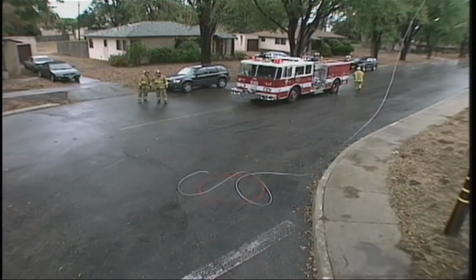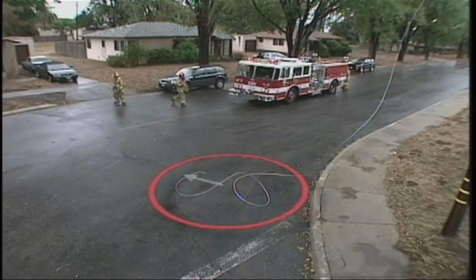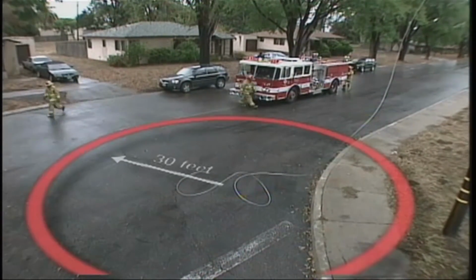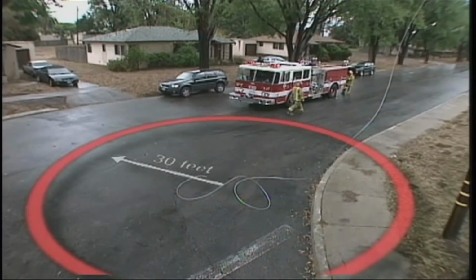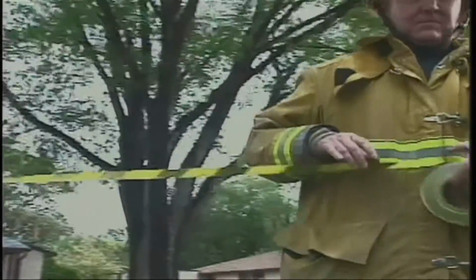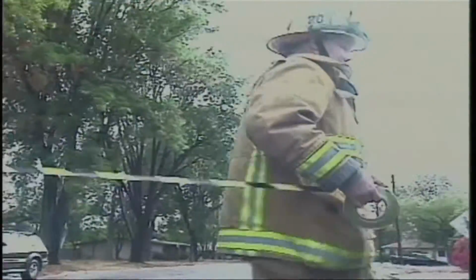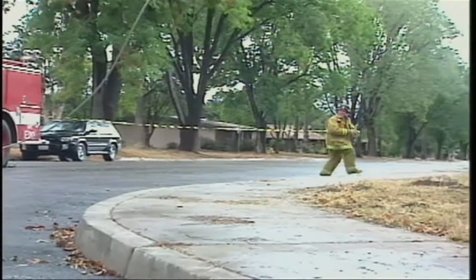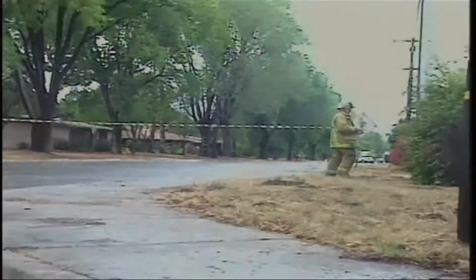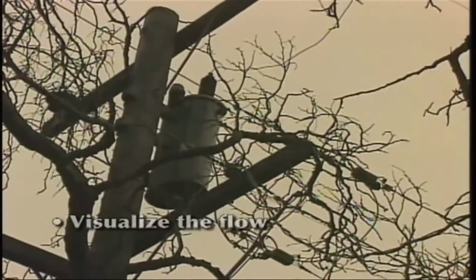On all down wire incidents, call Edison and set up a safety perimeter at least 30 feet away from the wire. Continue to secure the scene until an Edison employee or other authorized person arrives to eliminate the electrical hazard. It is important to visualize the flow of electricity from pole to ground. At night, use a light to trace all conductors from pole to pole until you've determined the full extent of the damage and the location of all the downed wires.